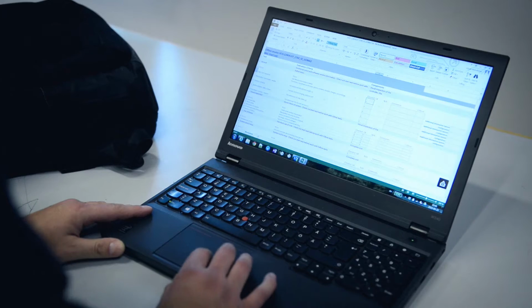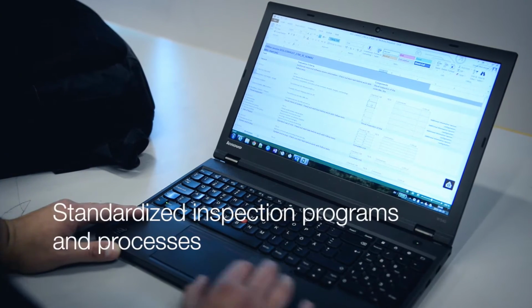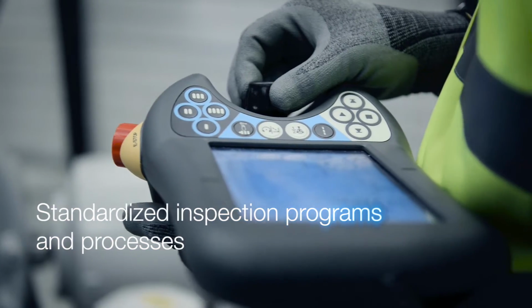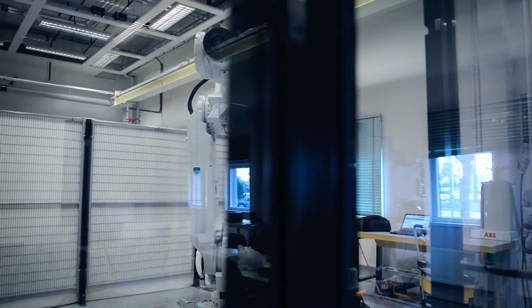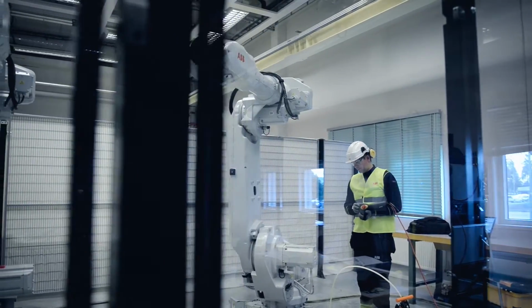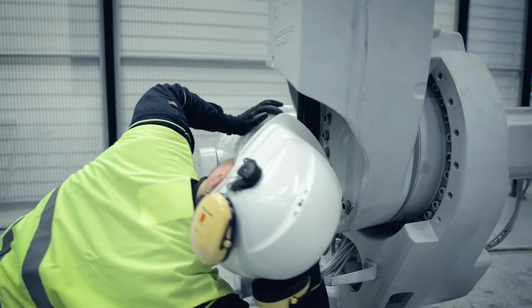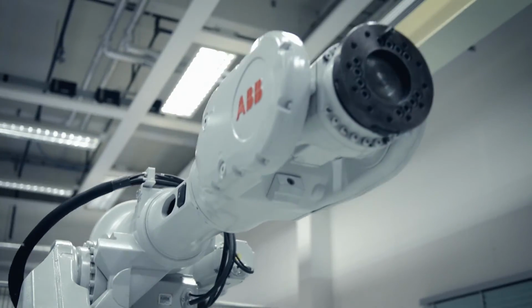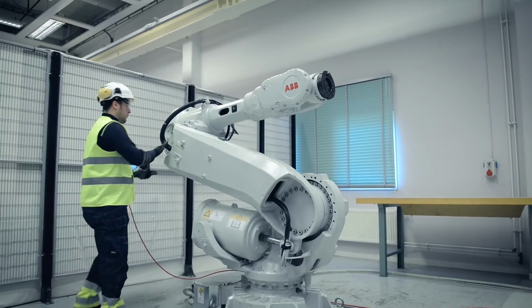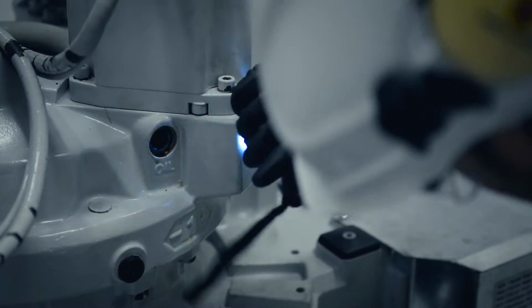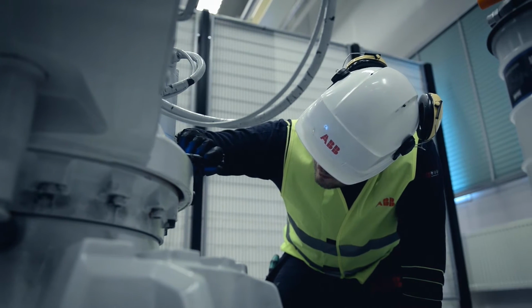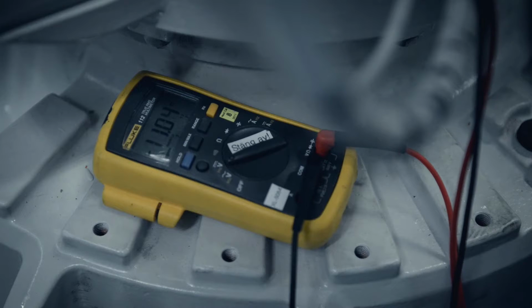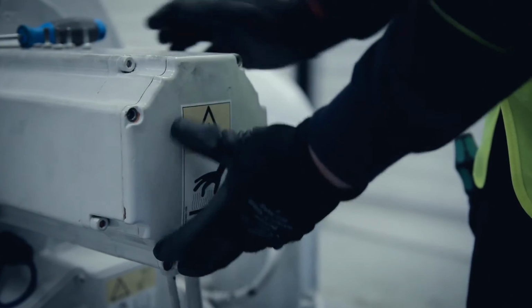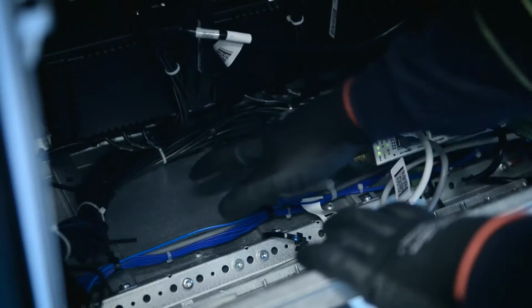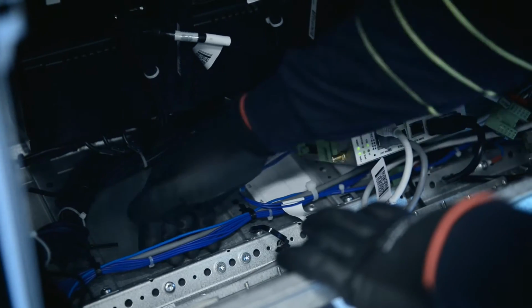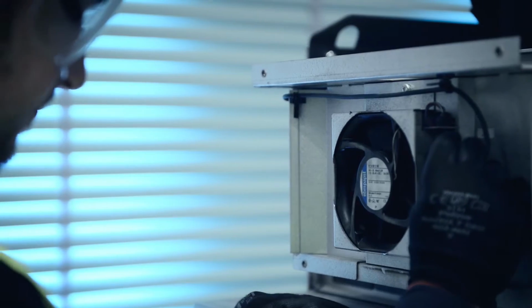Then the engineer commences the preventive maintenance tasks using a standard set of inspection programs and processes adopted by ABB across the world. An inspection program not only looks for parts that can be worn or perhaps damaged, but also provides the opportunity to clean any parts that may be affected by contamination and atmospheric conditions. For example, such things as contamination on the drive heat sinks of the controller can affect the cooling properties and thus the lifetime of the components within the controller.